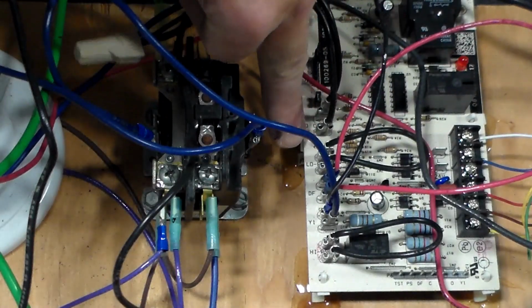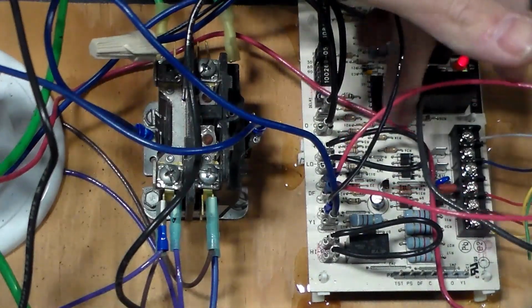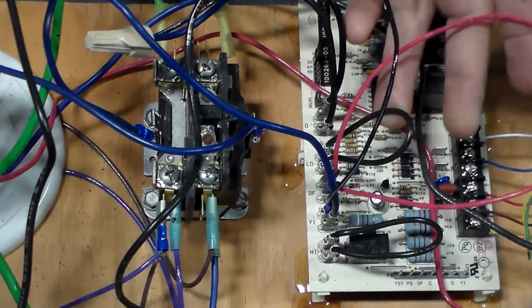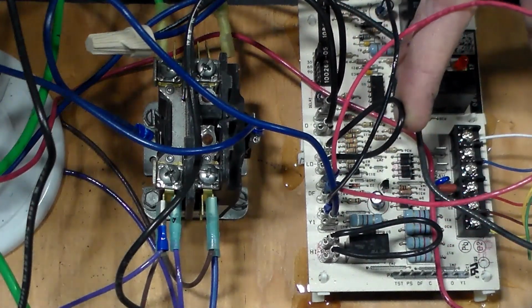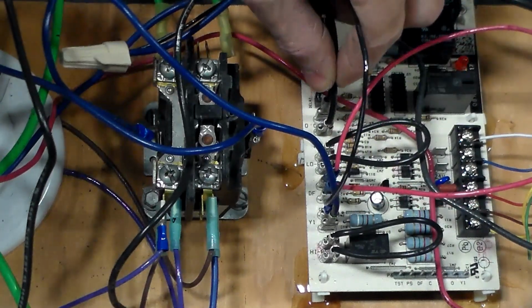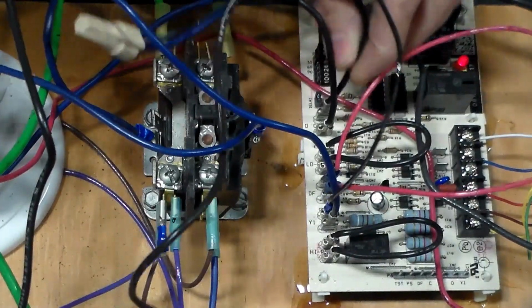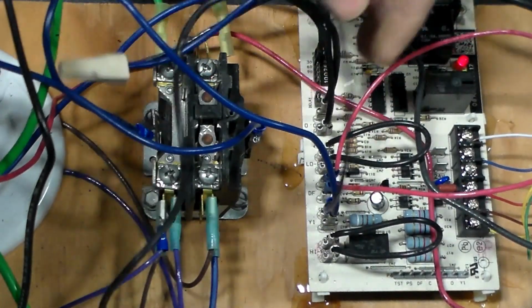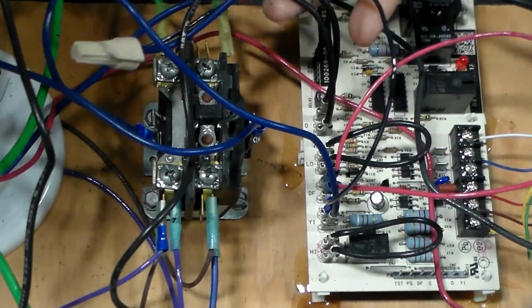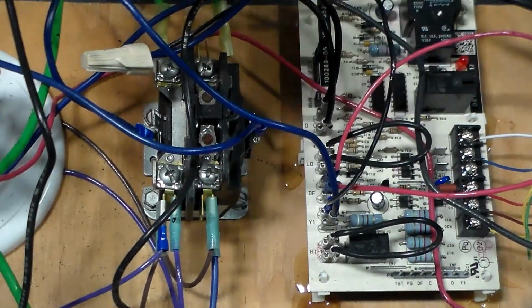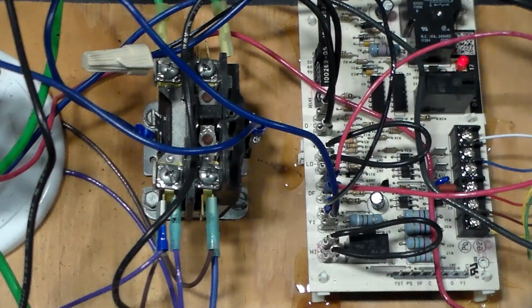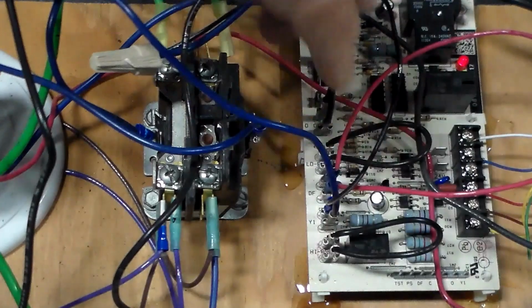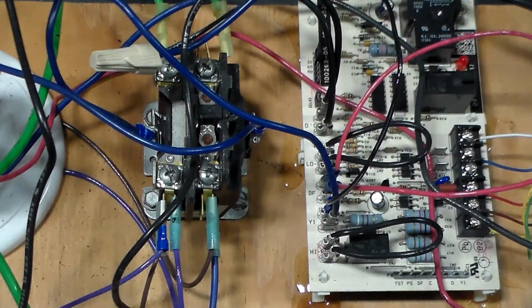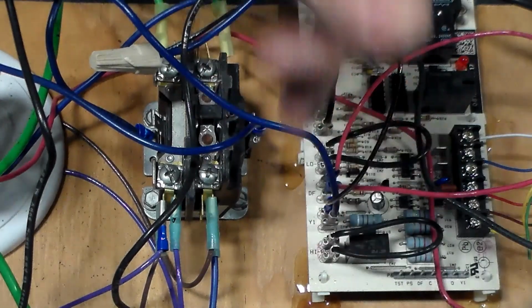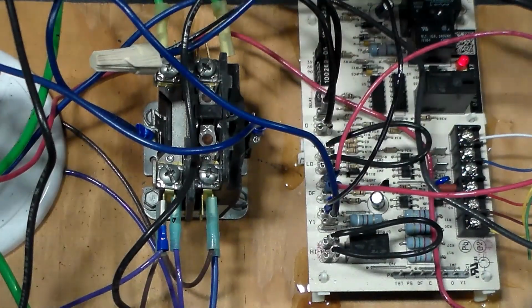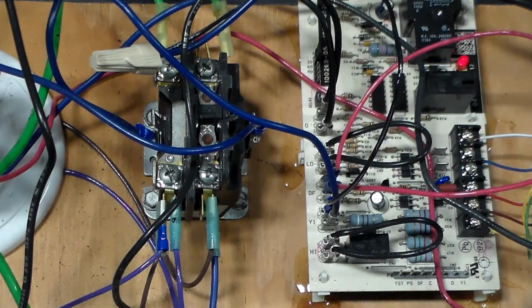The next two spades is your low pressure switch. And again, as you can see, I have that jumped out. So I'm just tricking this board into thinking everything's good on that. And then we have our O, which is our O out. And this would be our 24 volt. This one's not labeled common, so it doesn't really matter. Honestly, it wouldn't matter as far as the contactor or the reversing valve cares if you had these backwards, the hot and common coming off of here. You just need to run those two Y1 wires to the contactor, and the two O wires go to your reversing valve.